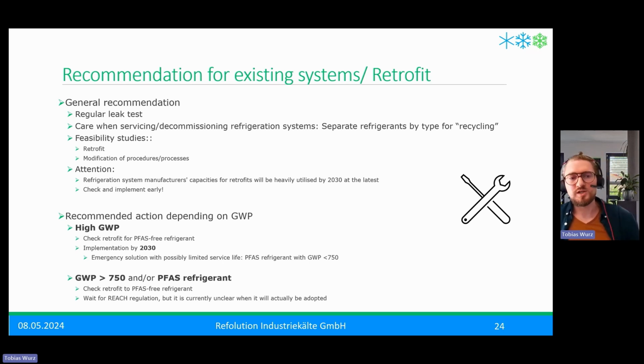Depending on the GWP, we have some recommendations. If you have a high GWP refrigerant, you should check a retrofit to a PFAS-free refrigerant, which mostly means a new unit. But since it's a high GWP unit, most of these units are already some years old. You should implement it by 2030 at the latest. So, as I said, you are not caught up in this big wave of market bottleneck. And maybe an emergency solution could be to use a PFAS refrigerant with GWP below 750, but with the risk that the service will be forbidden due to the PFAS ECHA REACH regulation.